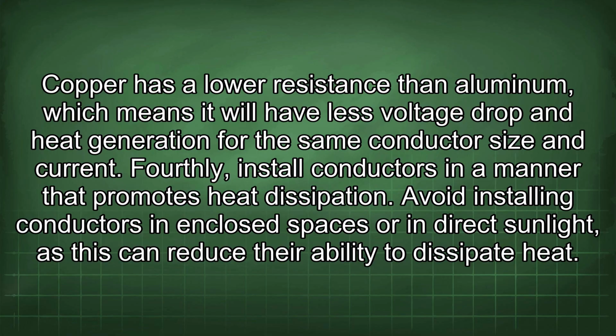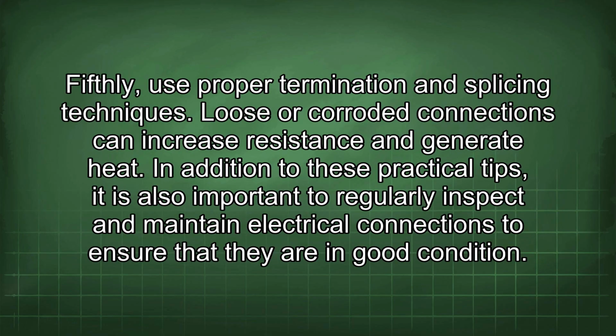Fourthly, install conductors in a manner that promotes heat dissipation. Avoid installing conductors in enclosed spaces or in direct sunlight, as this can reduce their ability to dissipate heat. Fifthly, use proper termination and splicing techniques. Loose or corroded connections can increase resistance and generate heat.